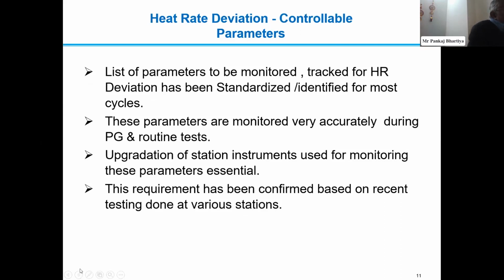So the list of parameters to be monitored and tracked for heat rate deviation has been standardized and identified for most of the cycles. And these parameters are monitored very accurately during the PG test and routine test. So those levels can be taken as the references, and accordingly our parameters can be tuned. Then upgradation of station instruments used for monitoring these parameters is very essential. There are not many, like your main steam temperature or main steam pressure or the vacuum or feed water temperature. So there are some, about 20 parameters which we need to take care of, wherein we need to put in high accuracy instruments and keep a track of them by monitoring the accuracy and the calibration of these instruments periodically. This requirement has been confirmed based on the recent testing done at various stations, because this is the area where we need to look while we make our heat rate improvement program.